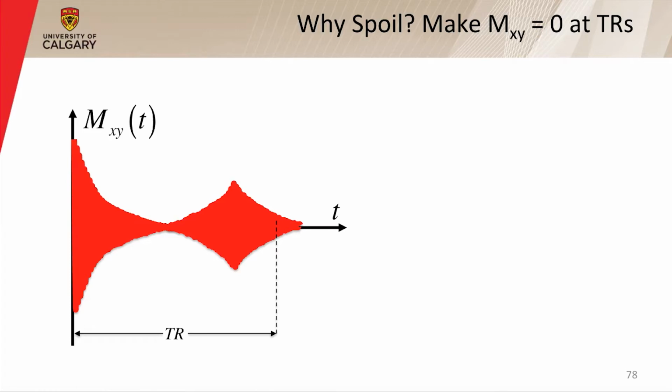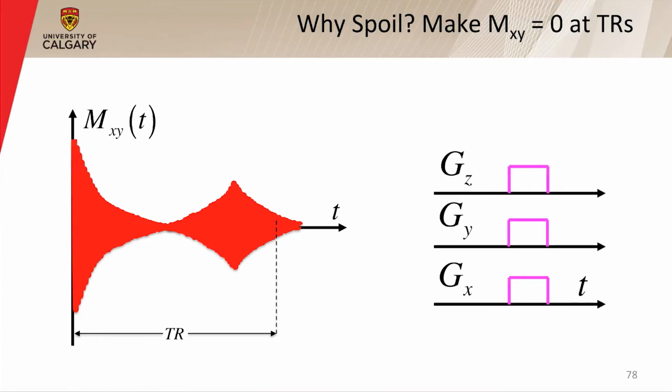And when we apply that alpha pulse, some of it's going to get tipped into the longitudinal plane, which will then be there to regrow and will start confounding the signal in subsequent alpha pulses. And so what we do is apply these gradients, sometimes in 3D, sometimes in 2D, that basically wipe out any residual signal after we've acquired the data from the center of this echo.